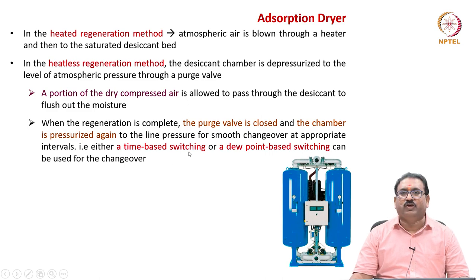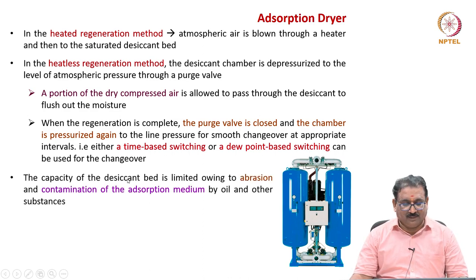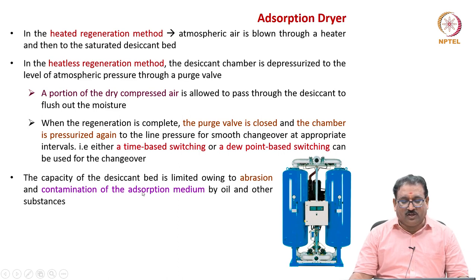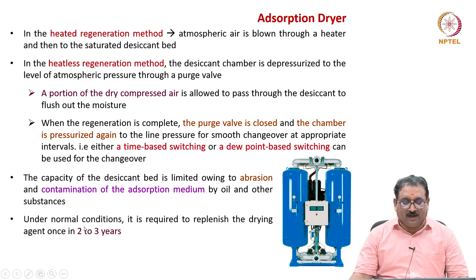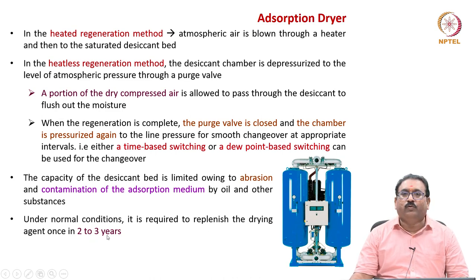Either time-based switching or dew point-based switching can be used for changeover. The capacity of the desiccant bed is limited due to abrasion and contamination of the adsorption media by oil and other substances. Under normal drying conditions, it is required to replenish the drying agent once every 2 to 3 years.